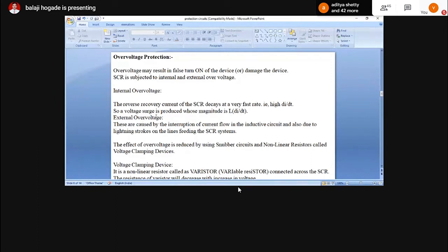That's why it is called the internal over voltage. Now, what is external over voltage? These are caused by the interruption of current flow in the inductive circuit. If the load is inductive, like a motor or a fan, and if there is an interruption in the current flow, it can be due to a lightning stroke on the lines feeding the SCR. Lines feeding the SCR means the input voltage.